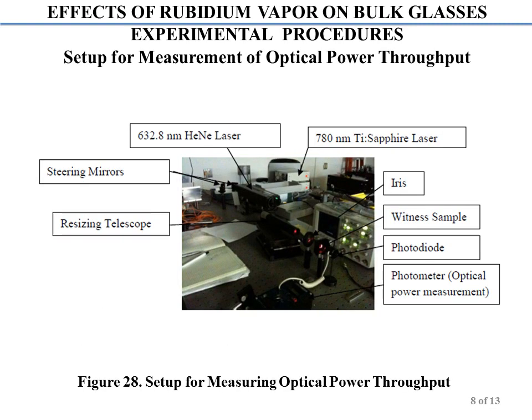As part of the measurement procedure, before each optical window is placed in front of the laser for optical transmission measurements, the power transmission at near and far field were first measured. A total of 26 measurements, minimum, maximum, and average power transmission, computed at near field, and 26 measurements at far field are taken before introducing either the reference unexposed optical window or the optical window exposed to rubidium vapor.